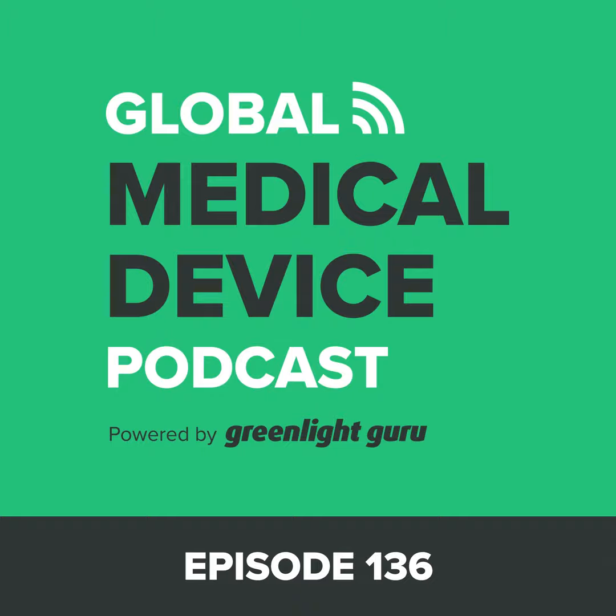exactly the same information. And the other thing that's very important, I think, for our audience to understand, John, is that the eSTAR does not affect in any way, shape, or form the regulatory burden of the medical device. In other words, the amount of testing, benchtop testing, clinical testing, and performance testing, and so on, is exactly the same, whether you use eSTAR or not. The only thing that eSTAR provides is a standardized format, a STED format, for those of you that are familiar with the PMA side of the world, to convey this information to the FDA. That's all it is. It does not reduce your regulatory burden in any way, shape, or form.